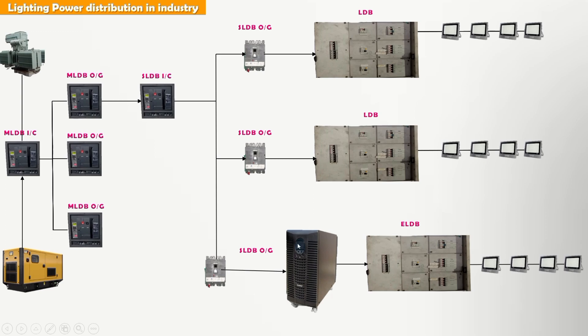How are LDB and ELDB segregated? Generally, the workplace has many light fittings to maintain the required lux level — inspection areas require different lux levels. During an emergency, not all lights are needed; only basic lighting is required. For example, if 10 lights are connected in an area, during emergency only 3 to 4 lights need to be on. Those 3 to 4 lights are connected through the UPS — that is called ELDB.